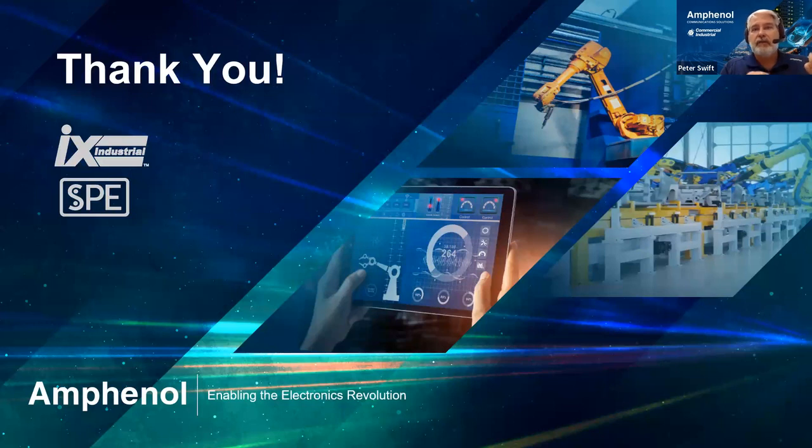As such, a lot of these devices don't really need to function at the much, much higher bandwidths and data rates that IX Industrial does, just because of the amount of data that's flowing. Because it's a dedicated device, you just don't need that degree of bandwidth. But it's not that it's not capable of that. At shorter distances, it's capable of relatively high speed. The big advantage of single pair Ethernet is that you can connect to devices out on the other side of your factory. It can go up to 1 kilometer.